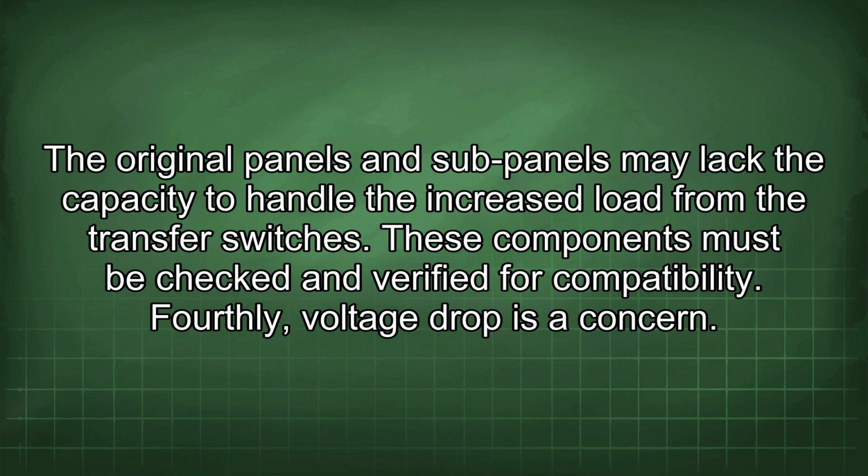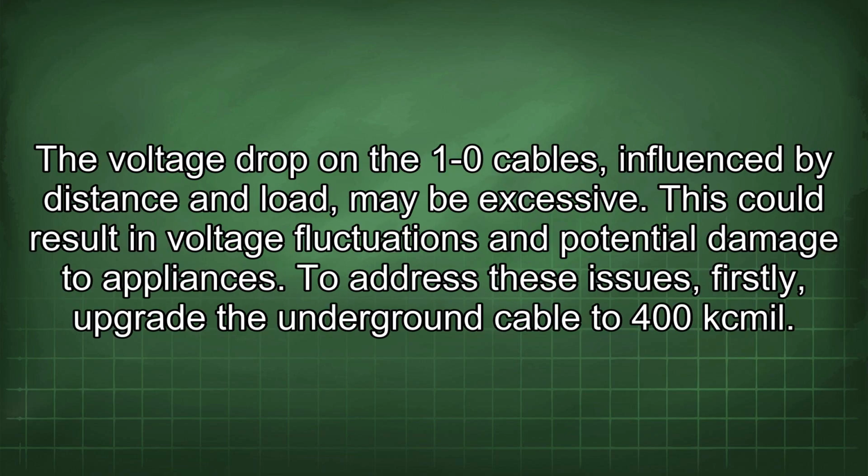Fourthly, voltage drop is a concern. The voltage drop on the 1/0 cables, influenced by distance and load, may be excessive. This could result in voltage fluctuations and potential damage to appliances.